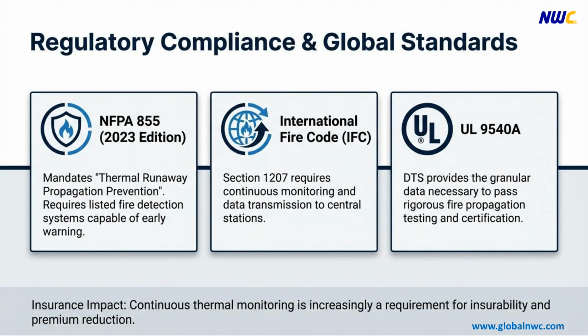Global standards such as NFPA 855 2023 edition and the International Fire Code IFC now strictly require early warning systems and real-time data transmission to prevent thermal runaway propagation. DTS solutions provide the high-resolution thermal data essential for UL 9540A certification, fully supporting the rigorous fire propagation testing process. By establishing a continuous thermal monitoring framework, operators can not only ensure regulatory compliance, but also achieve tangible economic benefits, such as improved insurance eligibility and reduced insurance premiums.